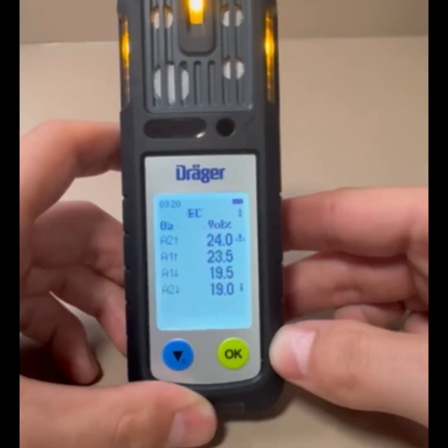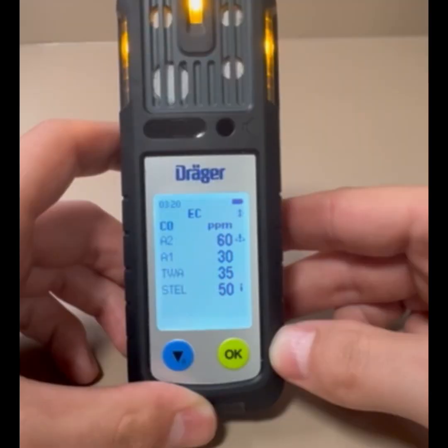For your LEL sensor or combustible gas sensor, you have two alarms. You have a low alarm of 10% and a high alarm of 20%. Next, you have your O2 sensor or oxygen sensor. This sensor has a two-alarm system, meaning you have a high alarm with alarm 1 set at 23.5 and alarm 2 set at 24. Then you have a low alarm with alarm 1 set at 19.5 and alarm 2 set at 19.